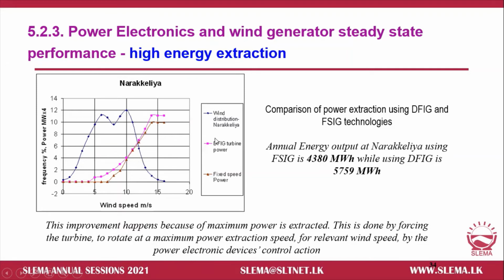When we compare fixed speed and doubly fed generators, of course the doubly fed turbines are a bit more expensive, but energy extraction is also greater. For a specific site, when we look at a fixed speed turbine, about 4,380 megawatt-hours per year can be extracted, but DFIG will yield about 1,500 more megawatt-hours. This is because its power electronics bring the rotor speed very close to the maximum power extraction speed for the specific wind speed, allowing it to extract more power at both low and high wind speeds.